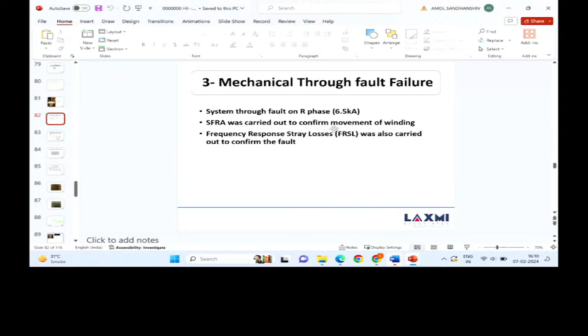This is an interesting case where the R phase was feeding a fault continuously in an ICT, and every parameter was normal. Only DGA was giving acetylene of 3 to 4 ppm, otherwise no such indications. SFRA was showing some deviation here. Based on DGA, SFRA and inductance measurement at site, with 5% deviation, the ICT was opened, and this was the buckling issue in the HV winding, of the R phase only. That buckling was in the IV winding, not in the HV winding, which we had predicted, and the same thing was realized.